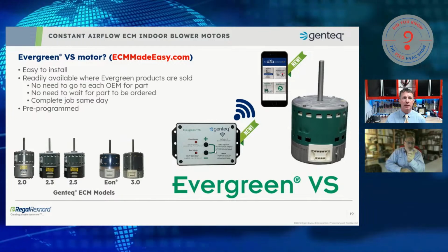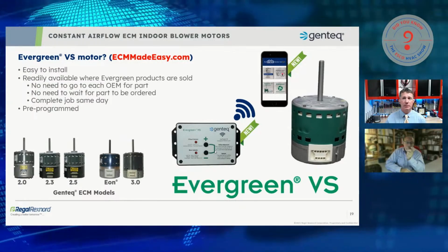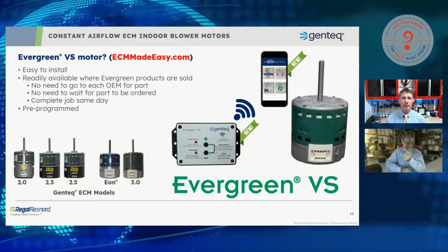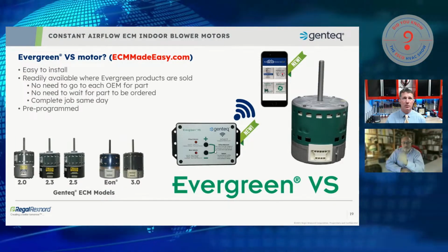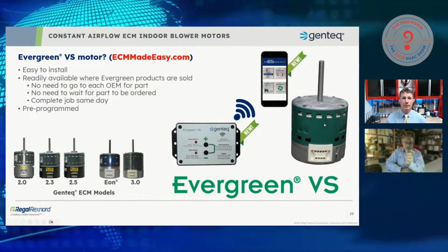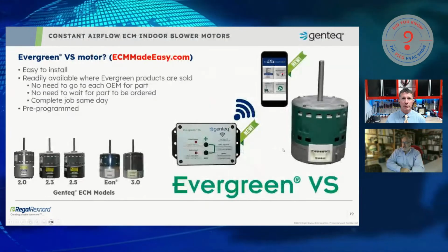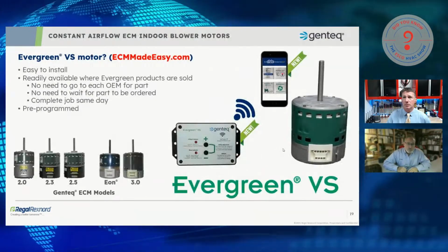One we sell for the TechMate Pro. You would only need that because it's actually a serial communicating motor. It just has a 16-pin, just needs to be repinned. So 2.5 would use the motor only with just a little 16 to 4-pin adapter. It would not use the UI. And then 3.0 would use just the motor only.